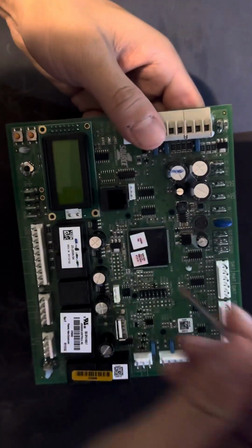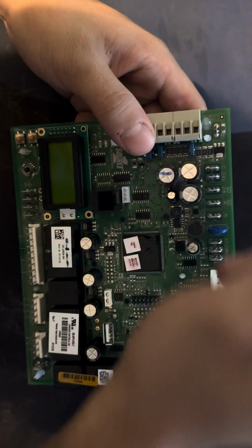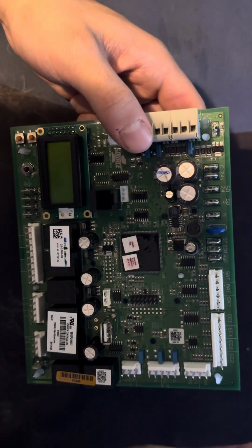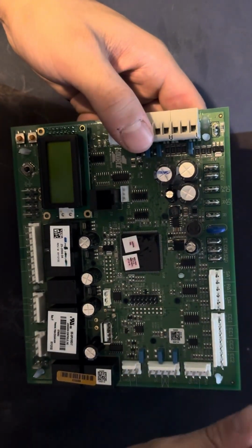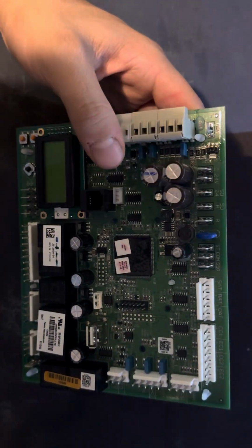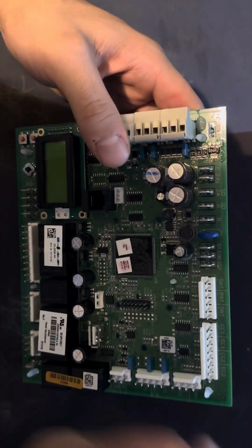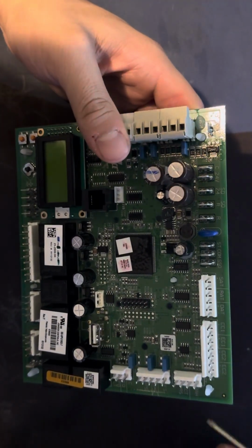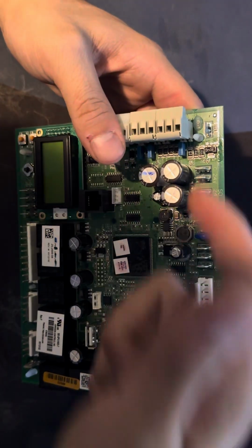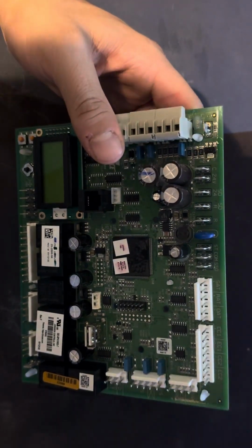Okay, now something real quick I forgot to mention: if you lose 24 volts on this terminal 3 times in 1 hour, this board will lock out all the outputs, for your cooling and for your heating, and it'll start displaying HS1 off due to the limit switch. So 1 time, 2 times, it's going to forgive you. It'll let the heating circuit lock out, but 3 times in 1 hour, you're done. Complete hard lockout from the main board. And like I said, a nuisance lockout could be something like that. If you drop to 18 volts, it's going to count as 1, probably. And then if it does it again and again in the same hour, same thing.